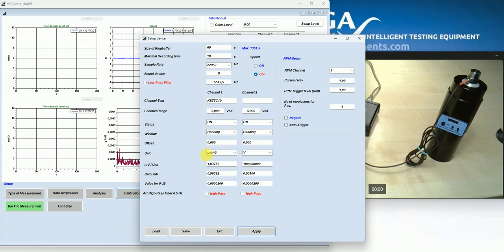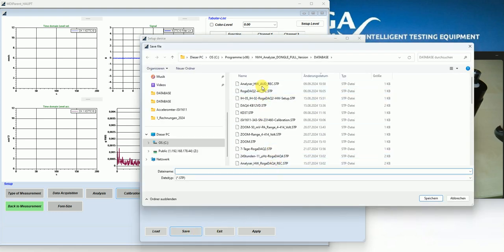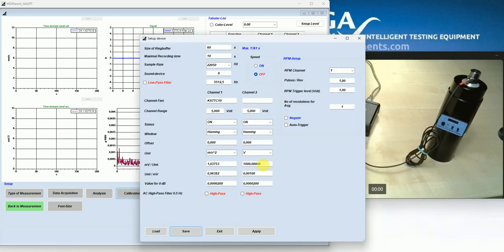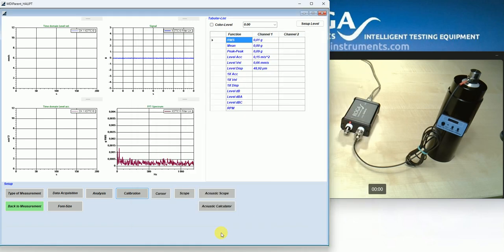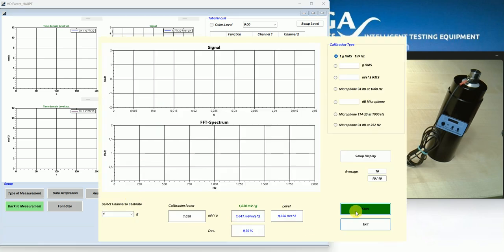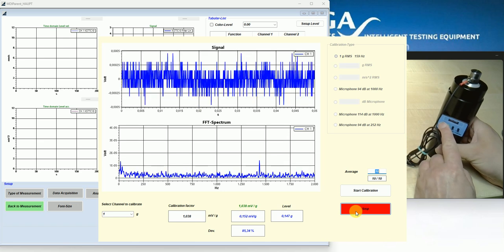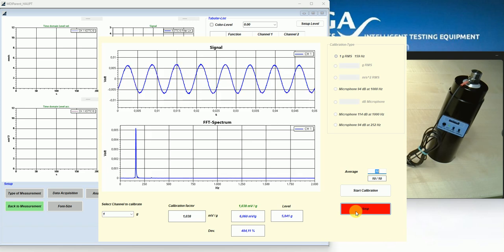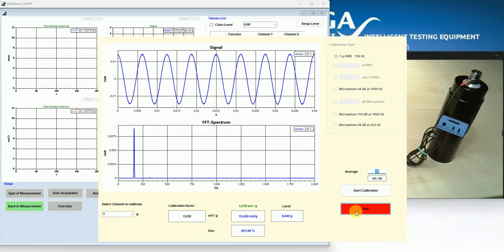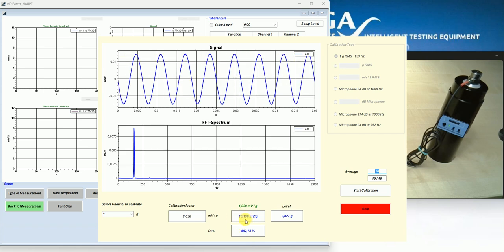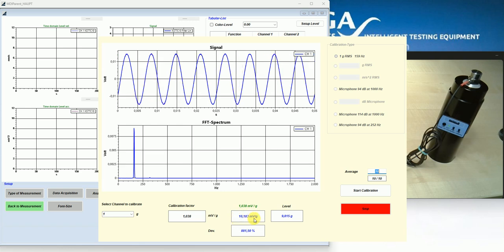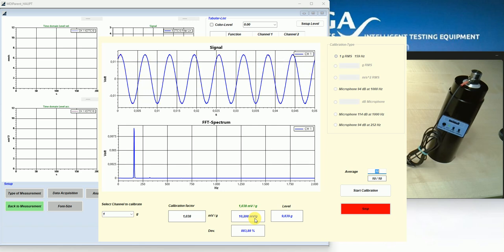This calibration value is copied to this menu, and I can save these settings. If I want to have the calibration result in G, then I can choose G here. Again, calibration menu, start calibration. Now we can see that the amplitude is calculated in millivolt per G, so the sensor has a sensitivity of 10 millivolt per G.